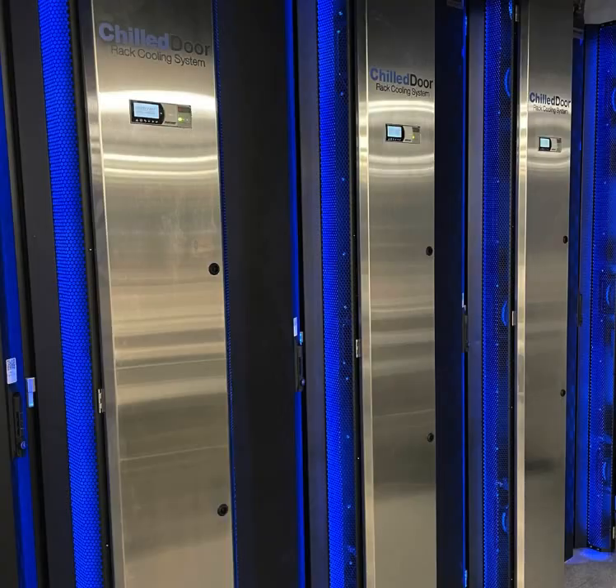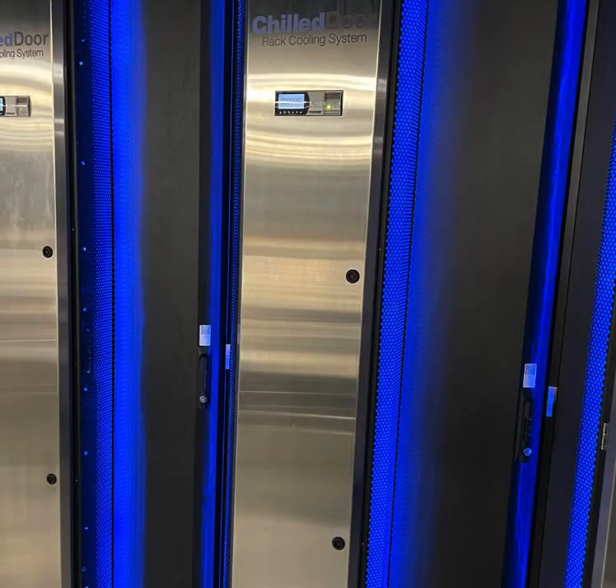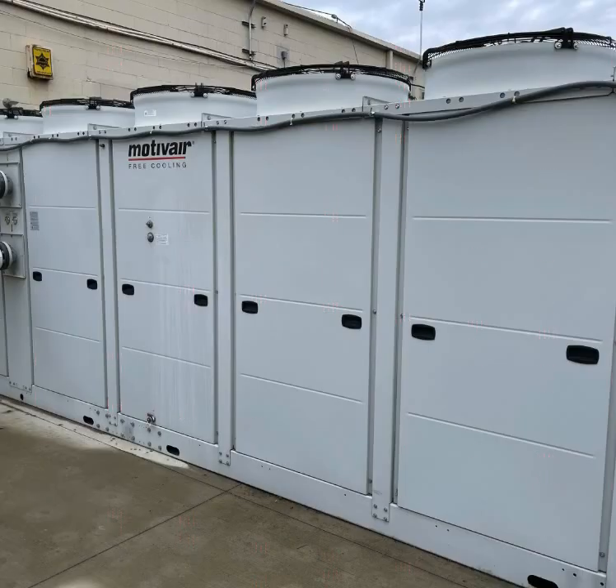Another thing we do differently is rather than cooling like a traditional data center with raised floors and big air conditioning units, called CRAC units, around the perimeter, we're doing cooling right at the rear exhaust of servers. We have a chilled water loop that goes from chilled doors behind the server cabinets all the way outside to our chilled water plants, efficiently accomplishing heat exchange right at the rear of the servers.